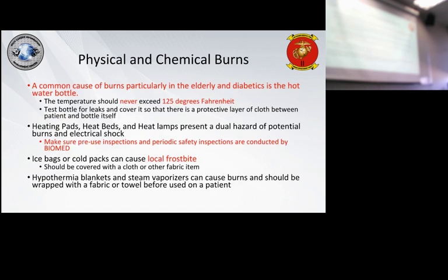A common cause of burns, particularly in elderly patients and diabetics, is the hot water bottle. It should never go above 125 degrees Fahrenheit. For heating pads, make sure pre-use inspections and periodic safety inspections are conducted by Biomed. Ice bags or cold packs can cause local frostbite. Gotta watch that.